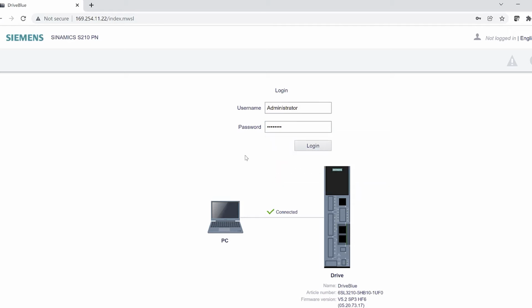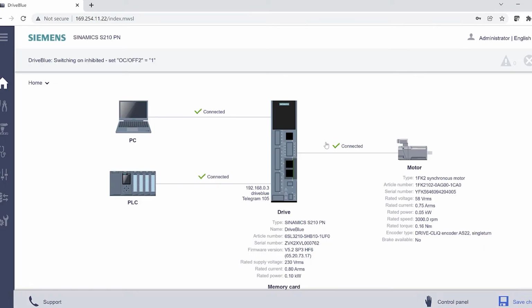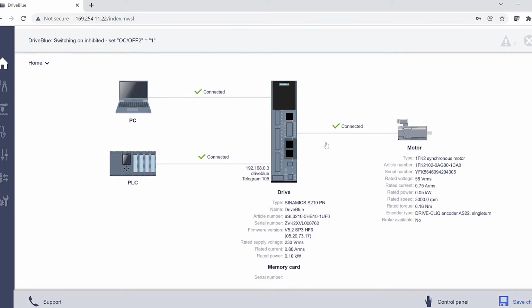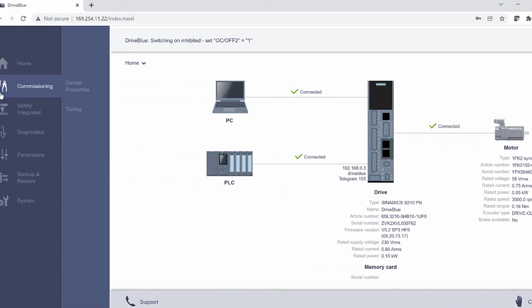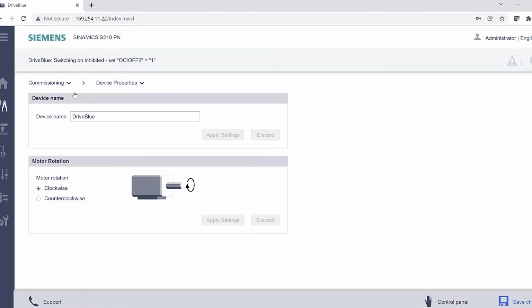Once logged in, a startup page shows all the components connected to the S210, including PLC and motor data. To the left of the screen, there are menu options. The Tools icon is for commissioning. Select this icon and then Device Properties. Here, you can enter the Profinet name and also confirm the motor's direction of rotation after it's installed. Then, you can go to the tuning page to perform the one-button tune.